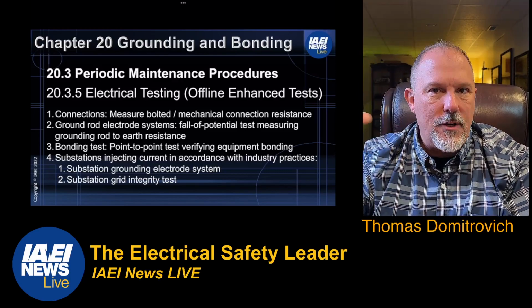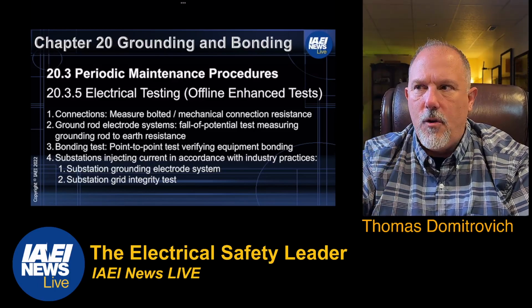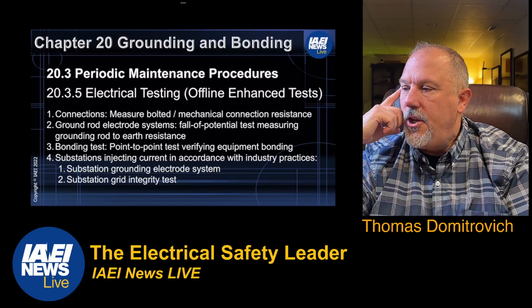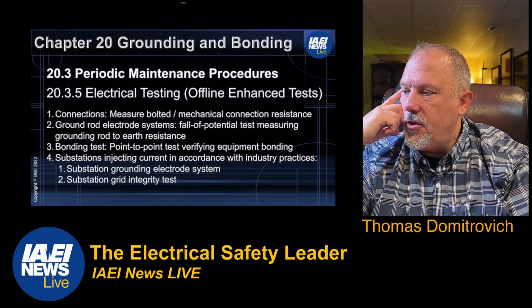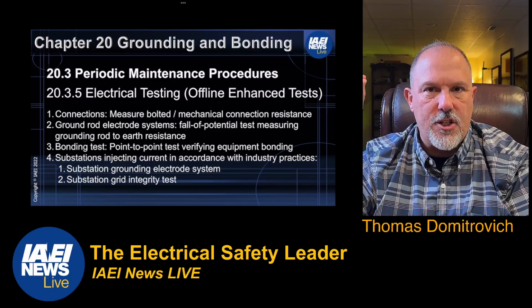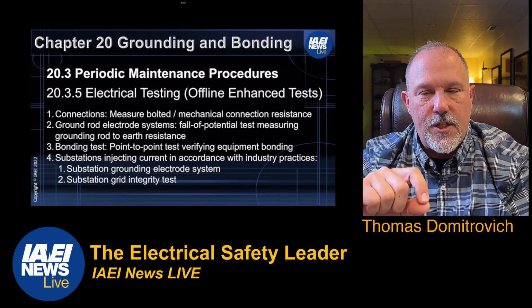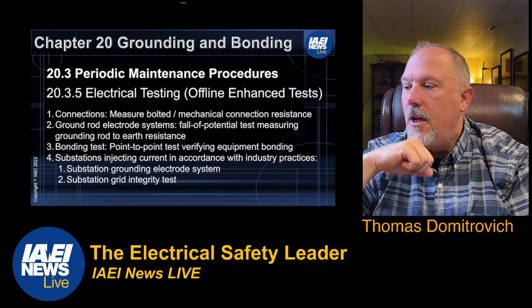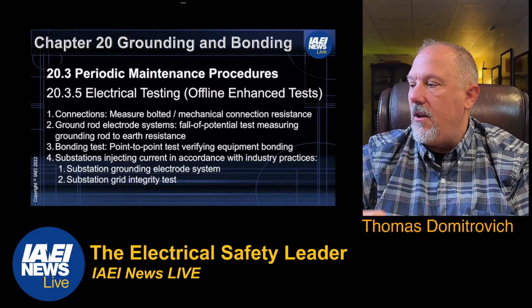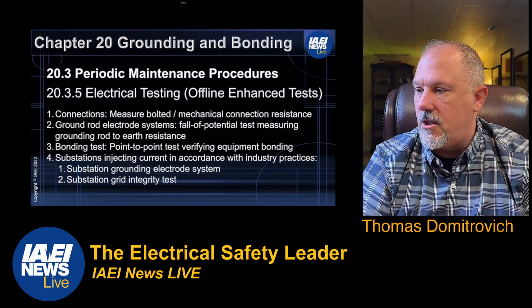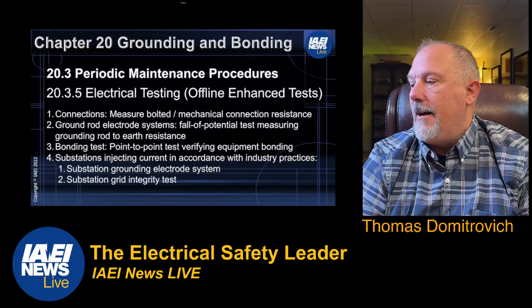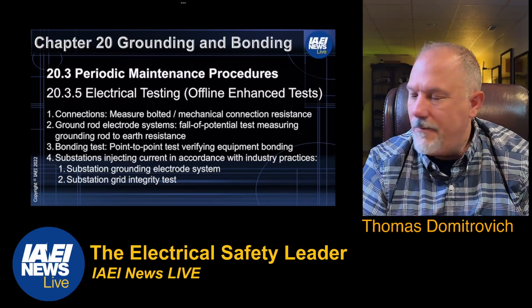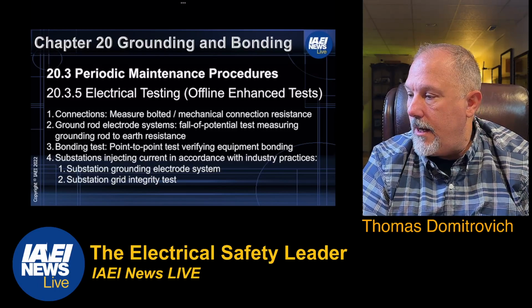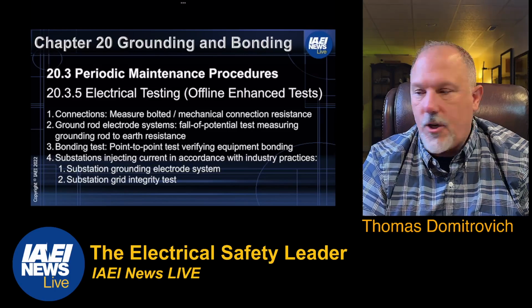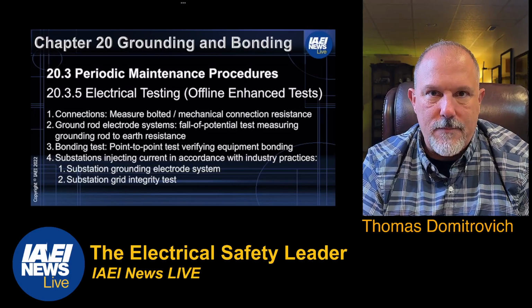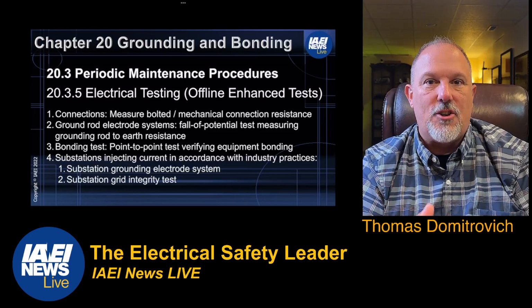Your visual inspections are going to help you look at the overall condition of that. You want to measure your bolted or mechanical connection resistance. So if you see something that is questionable, you can do an offline enhanced test. Your ground rod electrode system: fall of potential test, measuring ground rod to earth resistance. You're going to do a bonding test, point to point, verifying equipment bonding, and for your substation, injecting current in to test the substation grounding and bonding.